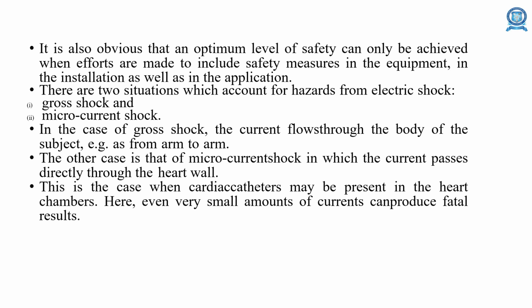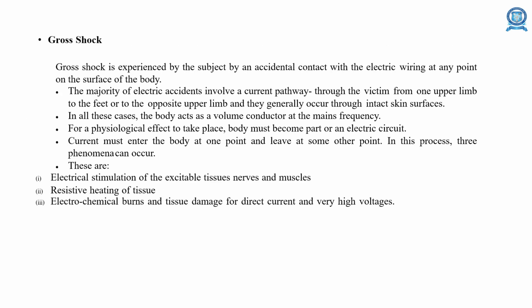There are two situations that account for hazards from electric shock: gross shock and microcurrent shock. In gross shock, the current flows through the body of the subject. Microcurrent shock is when current passes directly through the heart. Here even a very small amount of current can produce fatal results. Gross shock is experienced by the subject by accidental contact with electric wiring at any point on the surface of the body. In all these cases, the body acts as a volume conductor at the mains frequency. The current must enter the body at one point and leave at some other point.